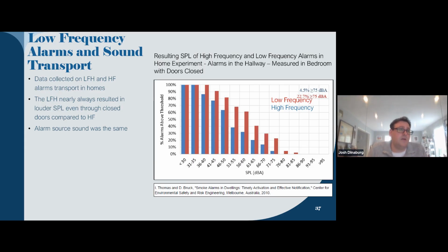So what you're looking at here is the percentage of the alarms that are audible given certain dBA thresholds. The red is the low frequency and the blue is the high frequency. If we're talking about getting between 70 and 85 decibels at the bed for closed doors and hallway installations, it's almost impossible for the high frequency alarms here, and much, much more likely for the low frequency alarms.